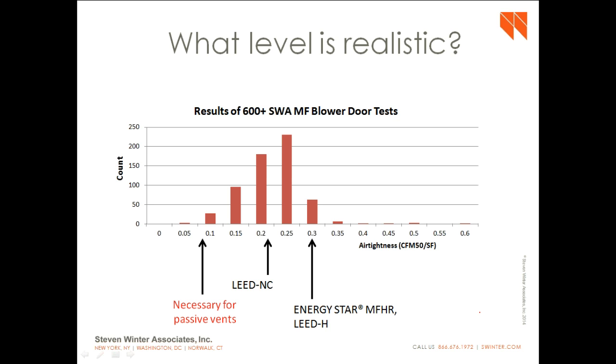We think that the air tightness necessary for passive vents to work is somewhere around here, close to where we are right now with these aerosol sealed apartments, but not sure that this is something realistic for the industry at large.